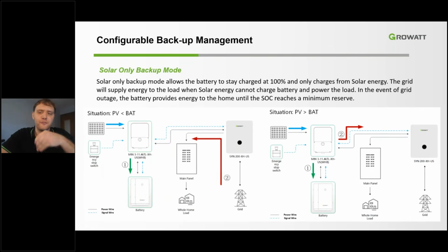There are many ways to actually configure the functionality of the backup system. One way is through solar only backup. In this scenario, the battery stays charged at 100% and only charges from solar energy. The grid can supply energy to the load during the night hours and allow the battery to be utilized only in emergency grid situations. In the event of a blackout, the battery provides energy to the home until it reaches a predetermined minimum reserve that is configurable by the customer, where a portable generator with 2-wire start-stop control can be implemented to charge the battery and power the customer's loads.